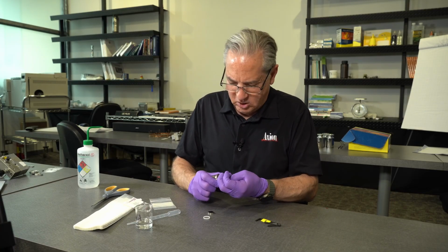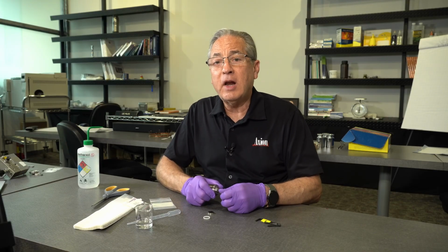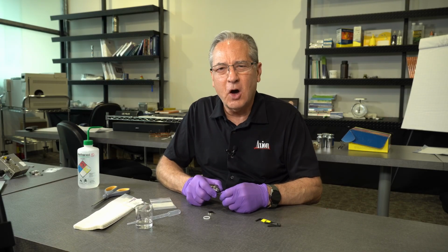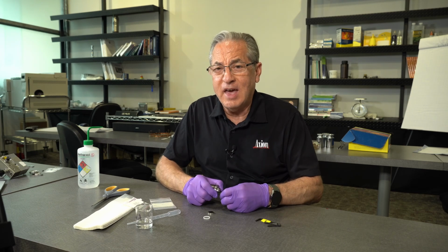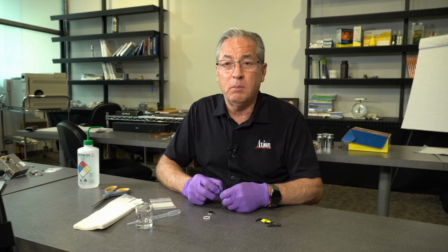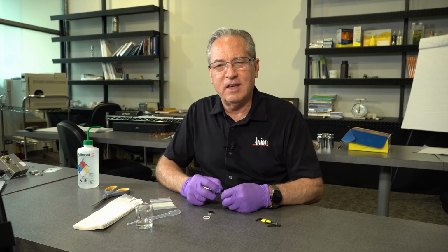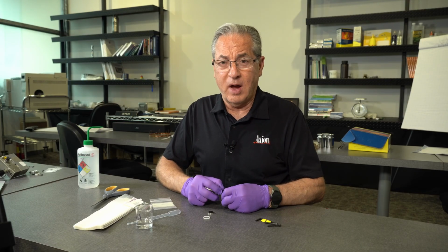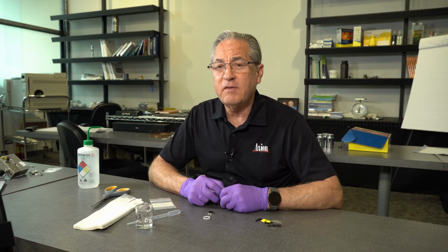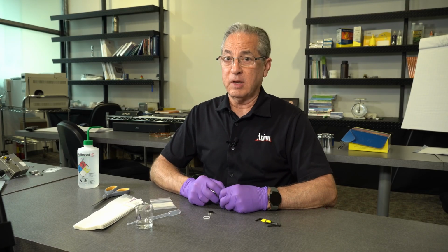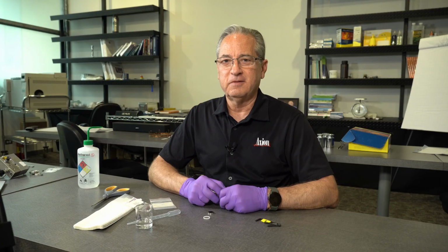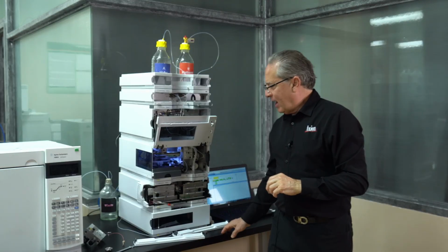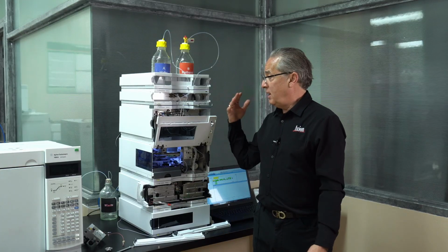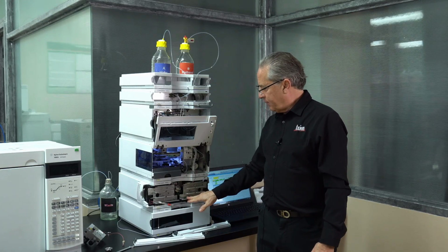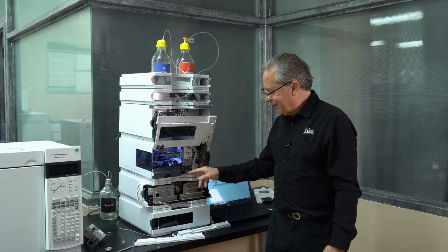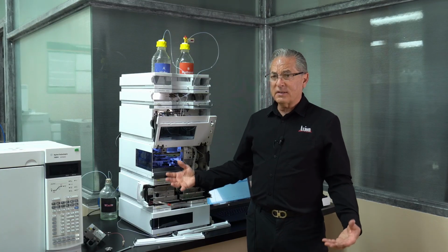So no matter which instrument type you have, you're going to have some sort of rotary valve in there inside the autosampler. You're going to find the same thing as the switching valve. If you have multiple columns, the column selection valve, the same thing, and we rebuild them all the same way. So that's rebuilding the valve on your autosampler, and that's going to help your reproducibility get back in line. So to me, that accounts for the majority of the maintenance in the instrument is going to be mostly in the pump. Next thing is going to be your autosampler, the rotor seal in the autosampler. The rest of the instrument, we'll talk about the columns as a separate part.